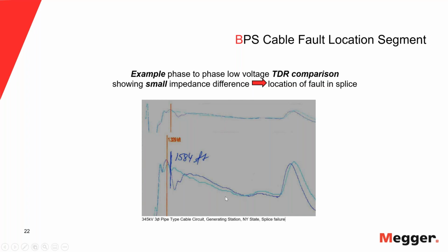And you see here on the right hand side, you see the big open, so that was the end of the circuit. Actually, the circuit went out underground from the power station up a hill to the switch yard, and then it went on overhead line out. Okay, so it was about I think 8,000 or 9,000 feet underground section up to that switch yard.